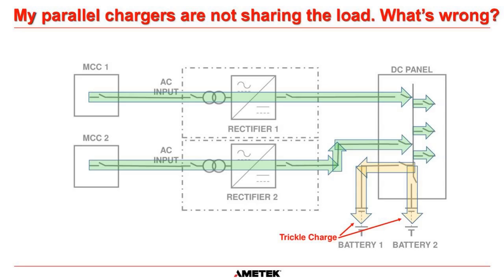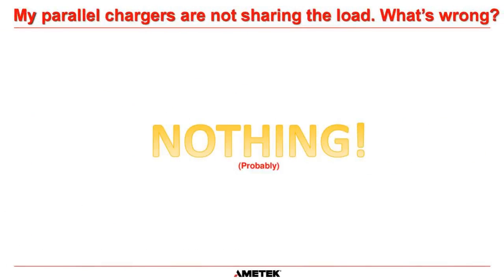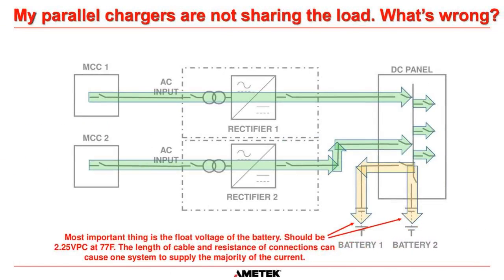Okay, what's this next slide? Oh, my parallel chargers are not sharing the load. What's wrong? My pet peeve. Nothing. Well, probably. It is very, very difficult to create a circuit, especially when the load on your system is very low, that will make your chargers share the load perfectly. Most charger manufacturers will say you have to have at least 5% load on your system before the parallel chargers will start sharing correctly. And that's if they have a load share circuit.